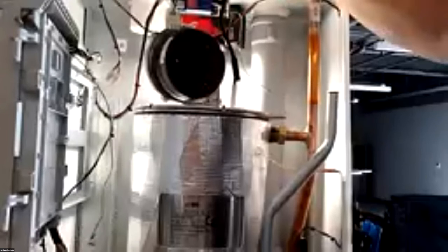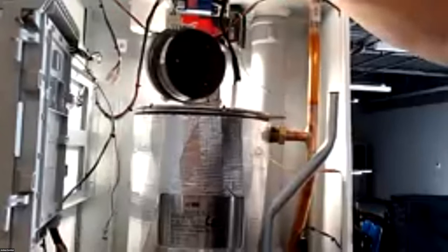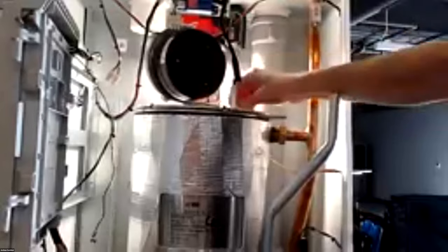When you go through the inspection and the cleaning, also make sure you get all your grounding wires back in. That's when we see guys reinstalling the boilers and leaving a grounding wire off and having failed ignitions. So make sure you get all those back on. And then, like I said, the flat plate, you can flush every year. There are a lot of contractors in this area that will just run it for 3 years and then swap them out.